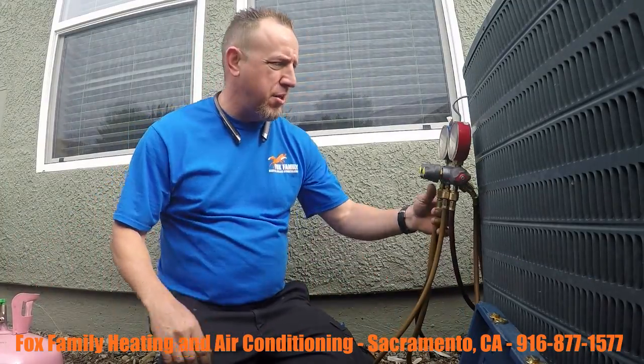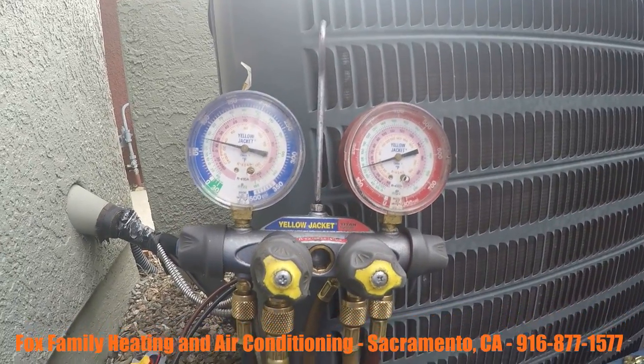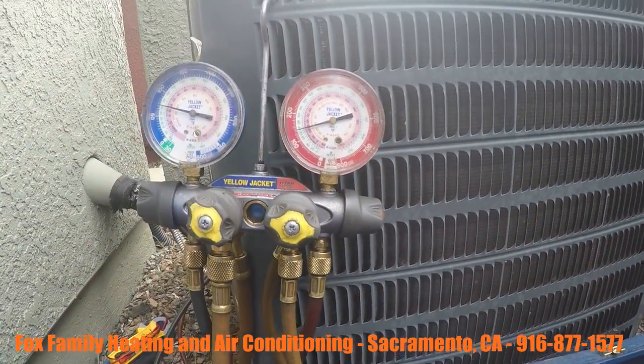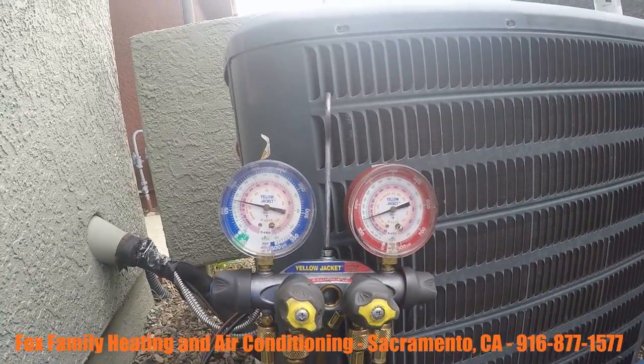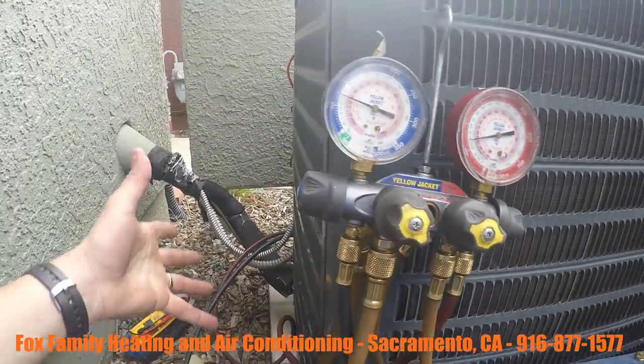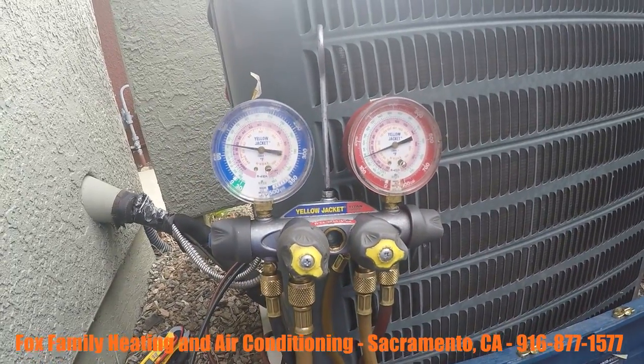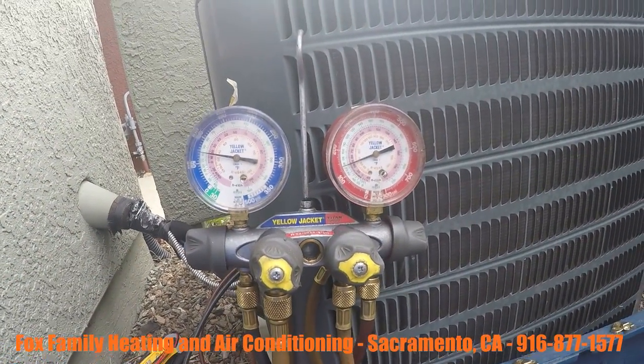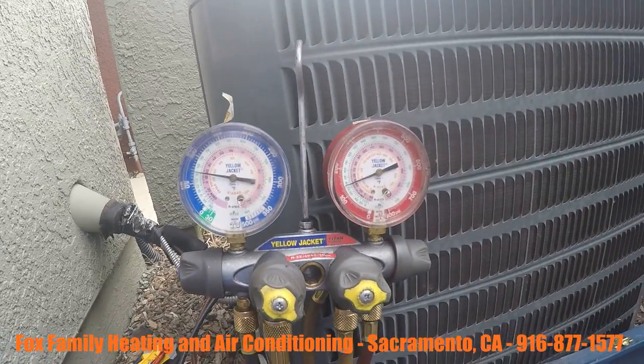Pressures are low. We're at around 20 degrees, around 15 degrees at the EVAP coil, and 50 degrees on the outside — it's pretty cool, right around 55 degrees outside. I can get a charge on it. What I'm looking for is around 30 to 40 degrees on the EVAP coil, and I'd like to get a cold suction line. There's definitely a leak here and we've got to find that as well. The goal for today is to get them charged up, because tomorrow's supposed to be like 80 and this weekend supposed to be like 90-95 degrees. We're gonna get the pressures up, get them cooling, and in the meantime we'll start the process of the leak search.